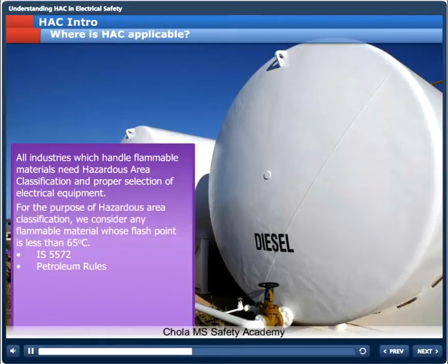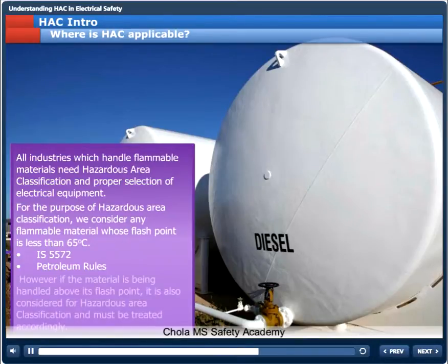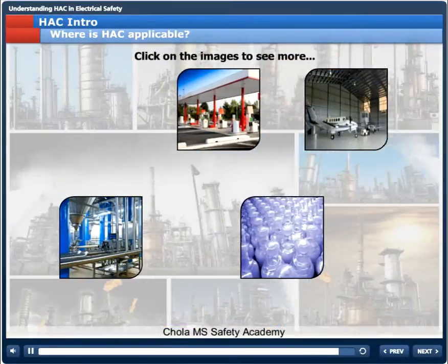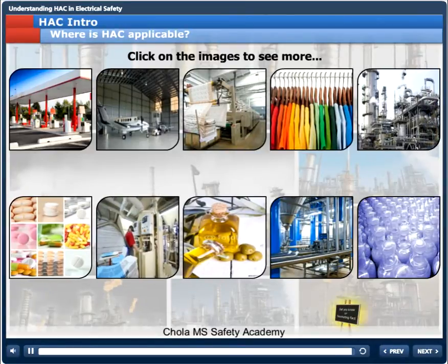For the purpose of hazardous area classification, we consider any flammable material whose flash point is less than 65 degrees centigrade. However, if the material is being handled above its flash point, it is also considered for hazardous area classification and must be treated accordingly. Click on the images to see more.